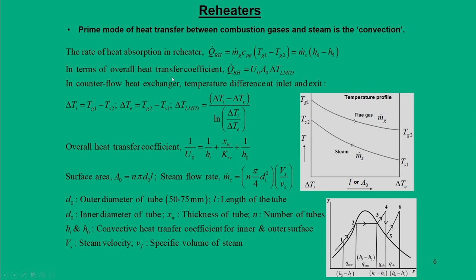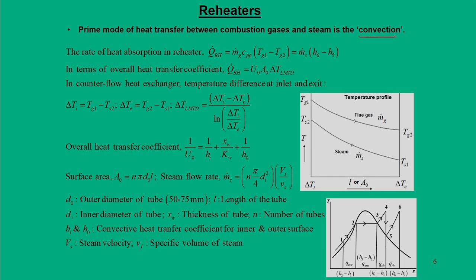In a reheater, similar to a superheater, the mode of heat transfer can be convection or radiation, but since the reheater deals with lower temperatures compared to the superheating unit, the prime mode of heat transfer is convection. For this reheating unit, the initial steam temperature is T_s1 and steam gets reheated to T_s2 — corresponding to T5 and T6. Heat is added from flue gas, whose temperature drops from T_g1 to T_g2 in a counter flow heat exchanger configuration, and the temperature profile is shown accordingly.